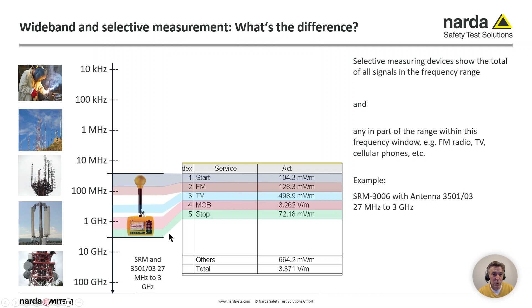So the selective radiation meter can distinguish between the different services, can even distinguish between different operators, between different cells, and so on. So the selective radiation meter is much more, I don't want to say intelligent, but you can get much more information out of it. So why still use broadband meters? Because they are much simpler to use, they are much lighter, they have a much higher bandwidth with a single probe, and they are also cheaper than a selective radiation meter. The minus is no information regarding frequency or service.